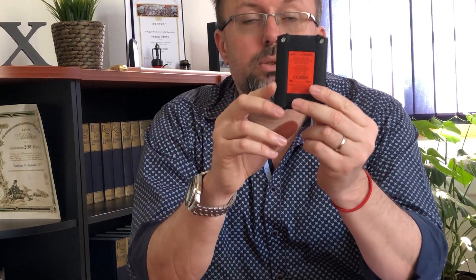A smartphone which comes into the EX environment needs to be EX certified. The minimum requirements include an EX certification, a declaration of conformity, a manual, and — importantly — a label on the device itself, so you can immediately assess whether it meets the requirements of the hazardous area classification.